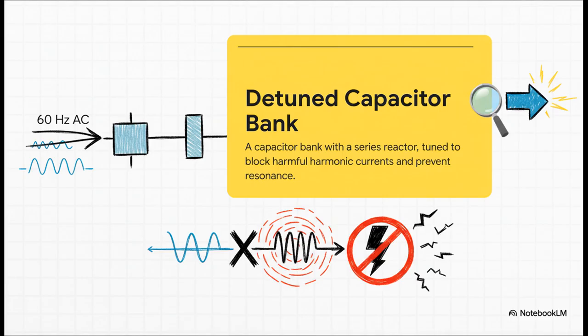Engineers just add a reactor, which is an inductor, in series with the capacitor. This little addition is carefully chosen so that the whole unit still corrects the power factor at our normal 60 Hz frequency. But at those higher, nasty harmonic frequencies, it actually becomes inductive and blocks those harmful currents instead of attracting them. It basically stops resonance before it can even get started.